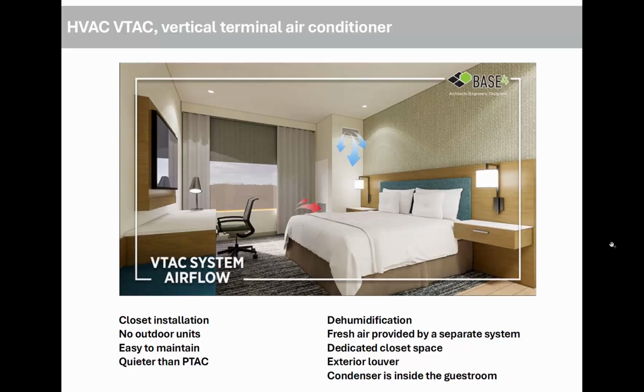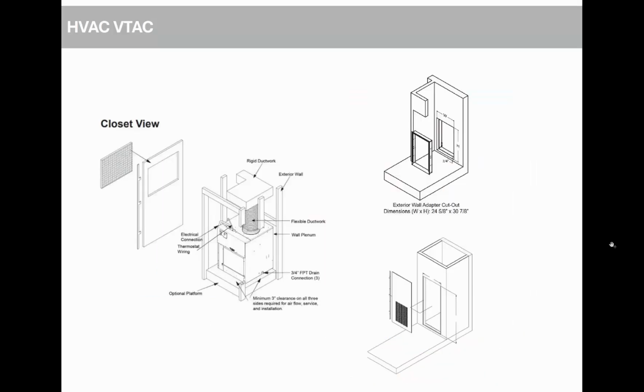So a couple of benefits for this is that since the unit is inside of a closet, it's a little quieter, you don't hear it, but the closet does take up space in the room, and it does need to be typically on an exterior wall where you're still going to have louvers on the outside that get the fresh air and vent the unit itself. It is quieter, it's easy to maintain. The PTAC unit, you have to take it apart if you need to maintain it. This one, you open up the closet and there's the unit exposed. And so it's a little bit of a step up typically from the PTAC. And then here's a few images of how that vertical unit might work.